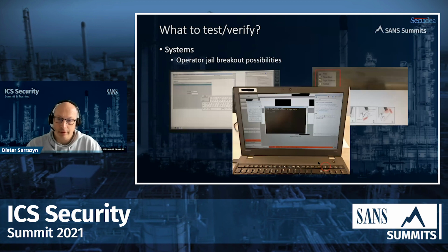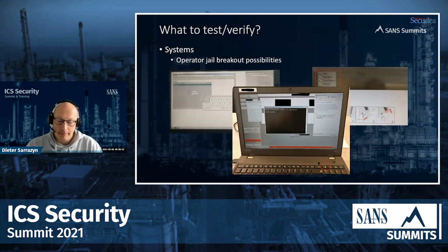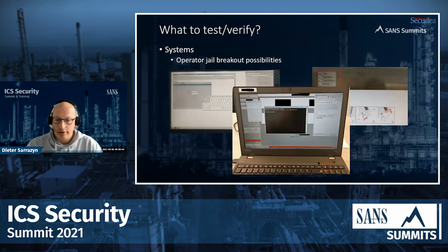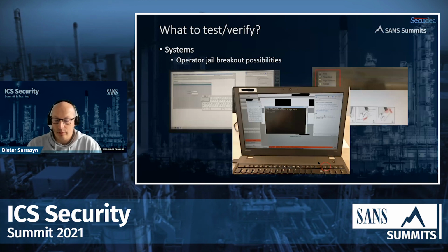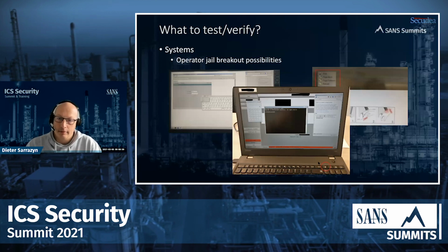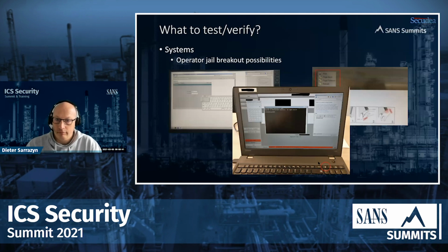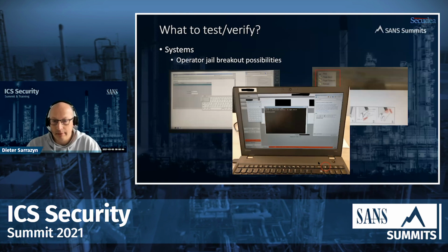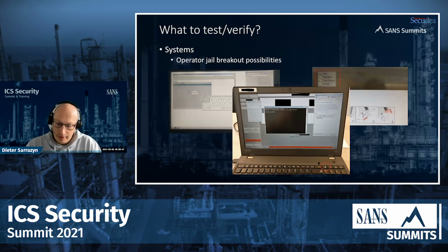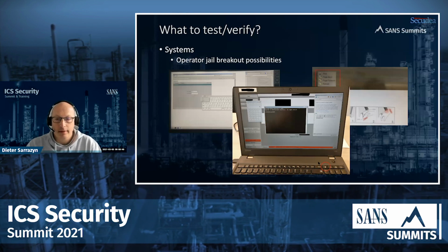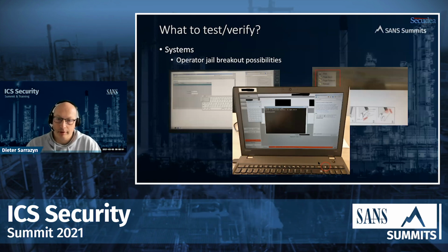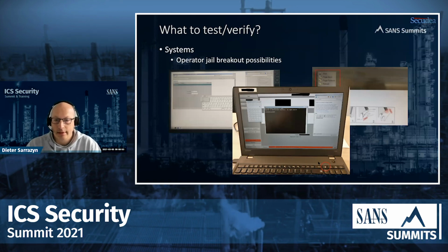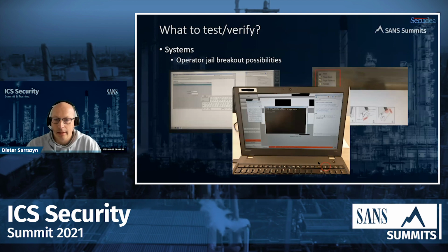I talked about this in an earlier presentation, but this is making sure that if there's operator jails, so if the operators are limited in what they can do on the systems, you verify if you can break out of those operator jails. Sometimes it's very easy, sometimes it's a little bit harder. In the SAT exercise I was talking about earlier on, this was the 3rd security SAT test I was doing for that environment.